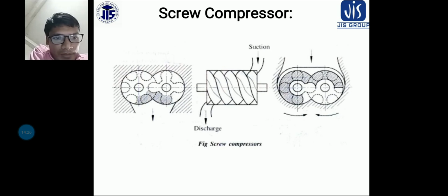The male rotor is normally the driving rotor. It is also called the driving rotor and consists of a series of lobes, usually four, along the length of the rotor, that mesh with similarly formed corresponding helical flutes, usually six, on the female driven rotor.